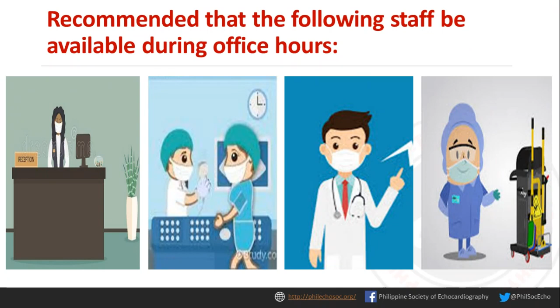Our existing ultrasound machines must be assigned for a specific purpose to minimize contamination and risk of transmission. If there are at least two echo machines, one is ideally dedicated for patients with suspected, probable, or confirmed COVID-19. If there is only one machine, strict disinfection measures must be in place and succeeding echocardiographic studies must be well spaced out, meaning you have to give enough time for disinfection of your machines before proceeding to another echo procedure. Such dedicated machines should be properly labeled and docked in dedicated and isolated rooms. It is also recommended to do bedside echo in all inpatients to avoid cross-contamination from patient transport. And ideally, machines used for inpatients and outpatients should be different.